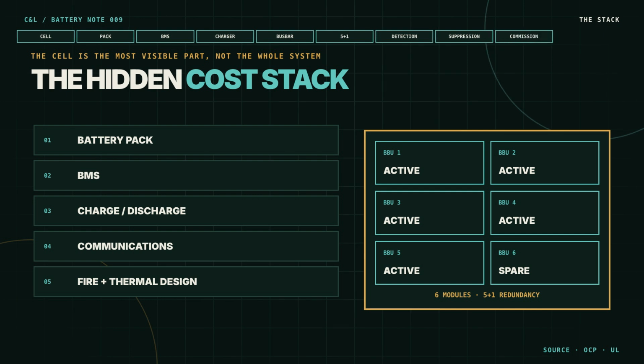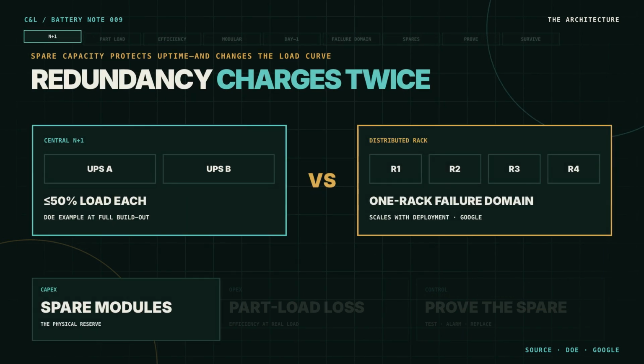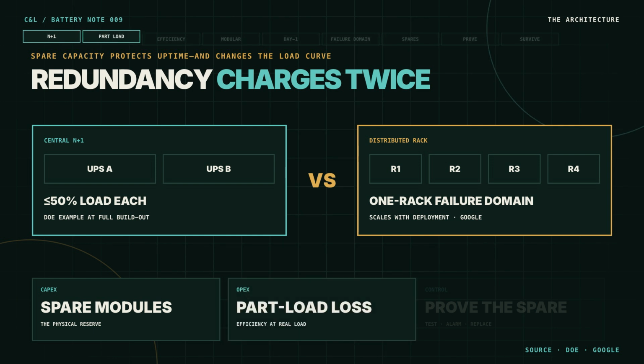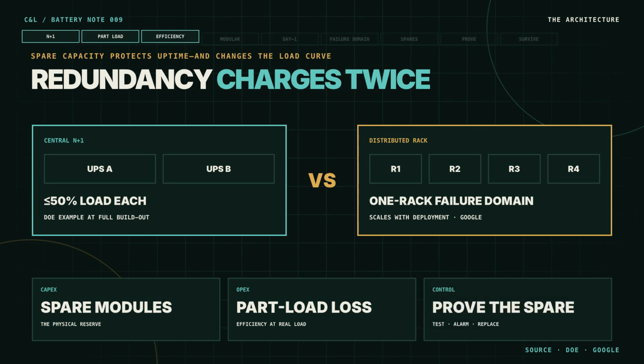Lithium-ion also adds a safety design obligation. Google says its battery backup designs undergo thermal runaway testing, while UL explains that large storage installations require fire propagation evaluation and site-specific protection. The cell is the most visible object, but the budget is really buying a controlled electrical and fire safety system around it. Reliability can increase capital cost and quietly reduce efficiency at the same time. The Department of Energy notes that a large UPS paired with an identical 100% redundant unit can operate at no more than 50% load, even at full build-out. Lightly loaded UPS equipment is often less efficient.